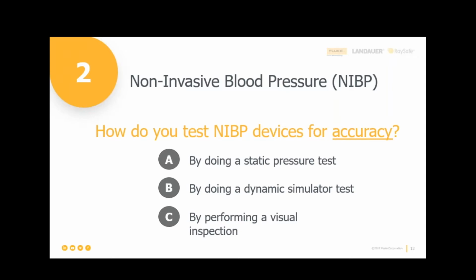Yeah. Well, what they said is, yeah, it's good, but it only tells you about repeatability. So let's say you send the monitor a dynamic NIBP simulation of 120/80. Whatever the monitor displays, because it's not about accuracy now, as long as it displays those same values every time you send 120/80, the measurement is repeatable. And that's all we can say about it. We cannot comment or assess accuracy because there's too many variables. We're not controlling the testing situation.